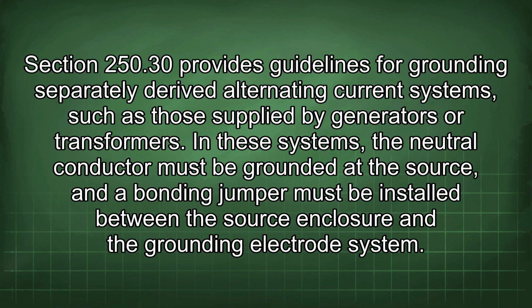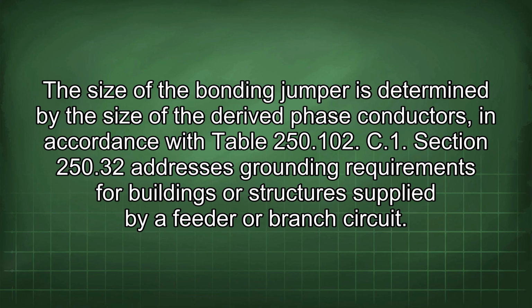Section 250.30 provides guidelines for grounding separately derived alternating current systems such as those supplied by generators or transformers. In these systems, the neutral conductor must be grounded at the source and a bonding jumper must be installed between the source enclosure and the grounding electrode system. The size of the bonding jumper is determined by the size of the derived phase conductors, in accordance with Table 250.102(C)(1).